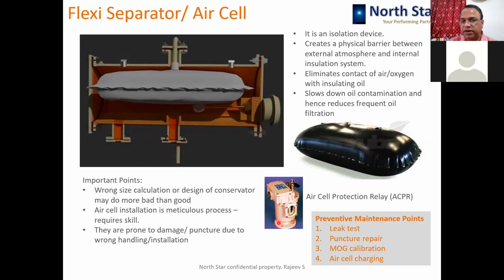Okay. A preventive maintenance point is that a leak test is to be done if you have some doubt about it. For puncture repair, normally a puncture kit is provided with the bag, and you must ensure that you get this puncture kit from your transformer supplier when you get the transformer. Normally it is left in the factory and rarely reaches the site, and of course the air cell supplier can also provide you the repair kits. It is very easy to repair. It is like repairing a cycle puncture. Okay, indicator calibration is to be done if there is some issue, and air cell charging. So these are the preventive maintenance points for the air cell.